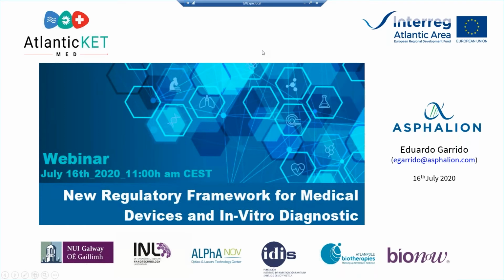Okay. And the report will work as a certificate. Yes, you will have to include it in the 3.2.R section of your dossier, and it will replace the certification. I mean, usually when you use a device that has already been certified, you place the certificate in the 3.2.R. In this case, since you're working with a device that has not been certified, you place the notified body opinion. Okay.